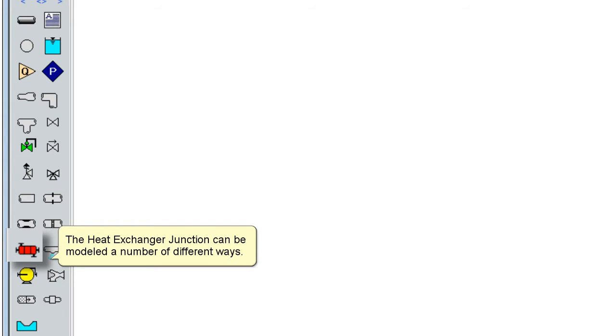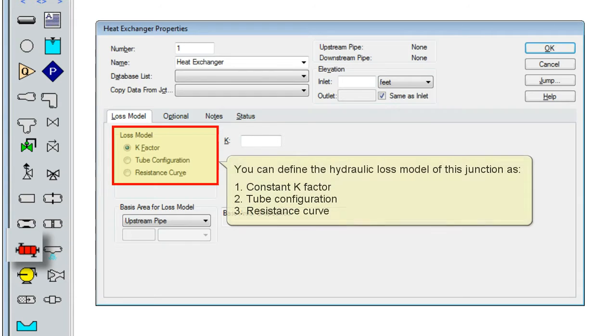The heat exchanger junction can be modeled a number of different ways. You can define the hydraulic loss model of this junction as a constant k-factor, a tube configuration, or a resistance curve.